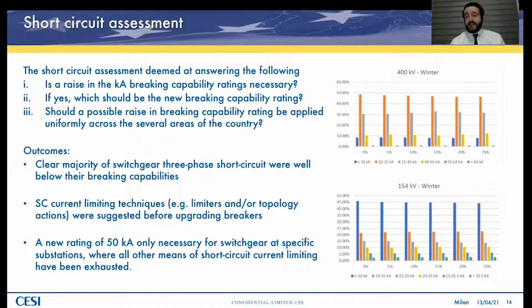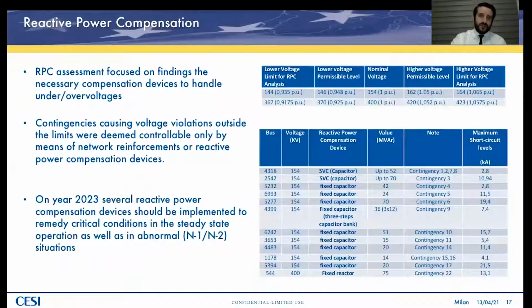Fortunately, the answer was that the large majority of the substations were already under, or were still under, the breaker capacity. So the short circuit current was not a concern, as long as it would not have been increasing more in the future. Only some substations should have been equipped with new circuit breakers, and the new breaker rating that was identified was 50 kiloamps for those substations.